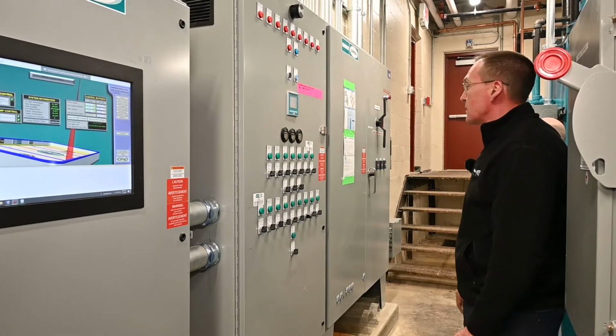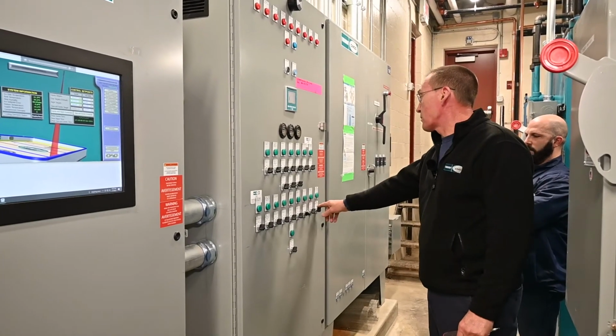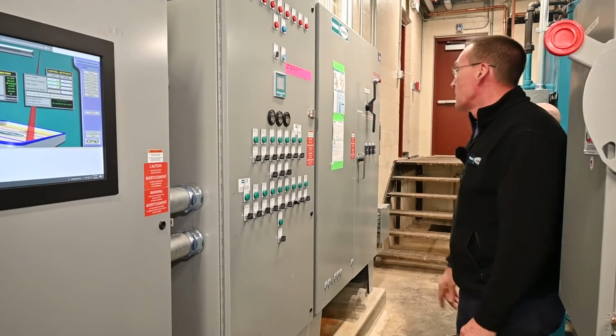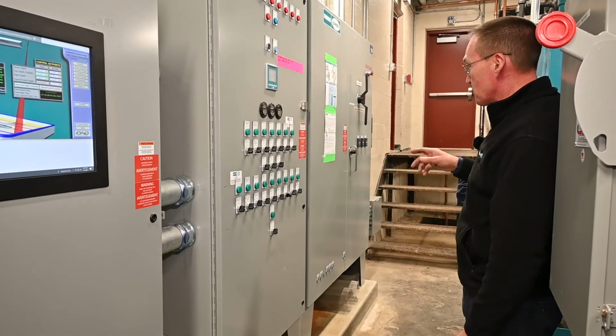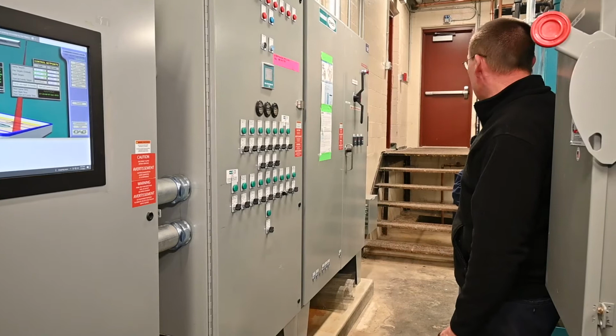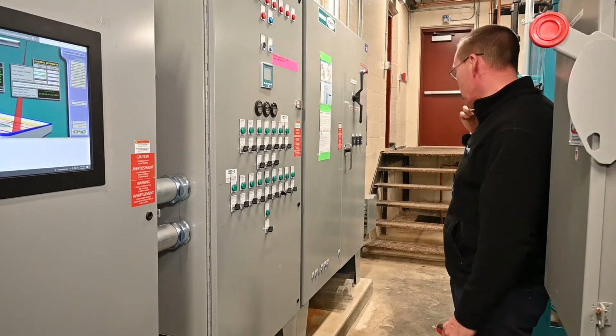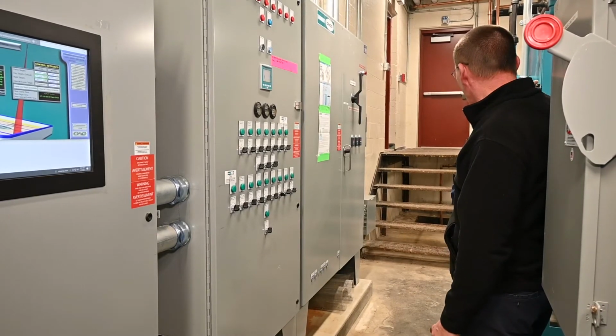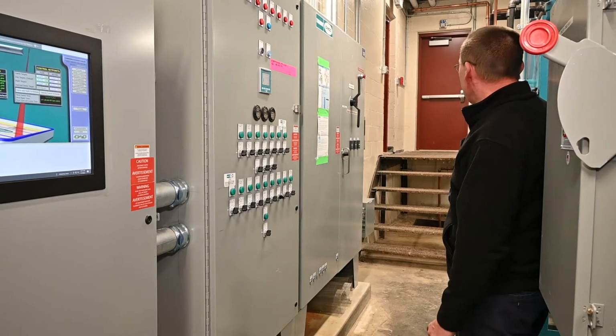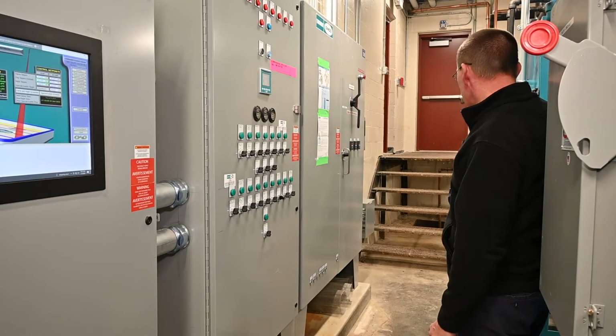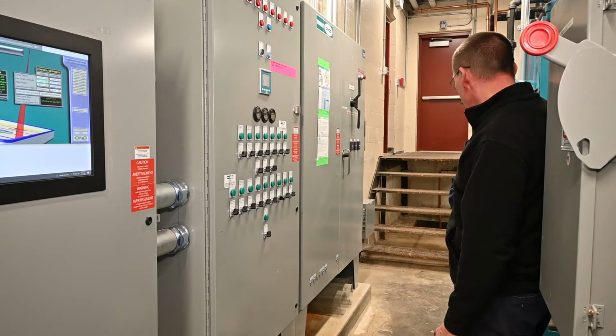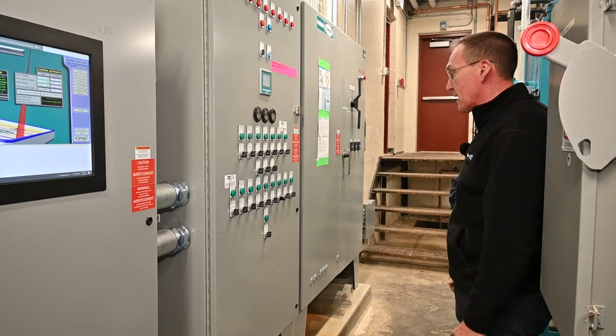All right? And the last and least is the Zamboni water pumps, P7 and P10. Those two small circulator pumps, which we'll show you in the Zamboni room, are pulling that warm glycol. When the package starts, it will pull that heated glycol to the plate heat exchangers in there and preheat that water.